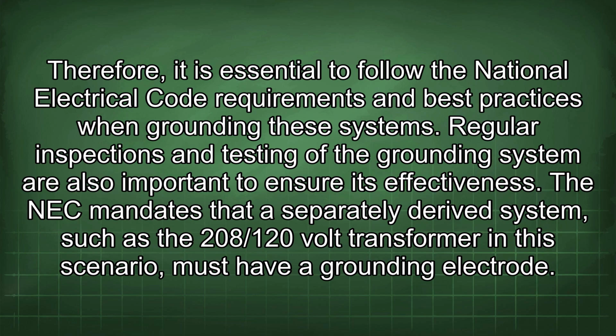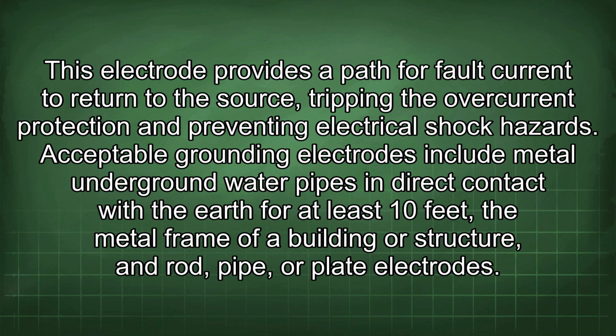The NEC mandates that a separately derived system, such as the 208/120-volt transformer in this scenario, must have a grounding electrode. This electrode provides a path for fault current to return to the source, tripping the overcurrent protection and preventing electrical shock hazards. Acceptable grounding electrodes include metal underground water pipes in direct contact with the earth for at least 10 feet, the metal frame of a building or structure, and rod, pipe, or plate electrodes.